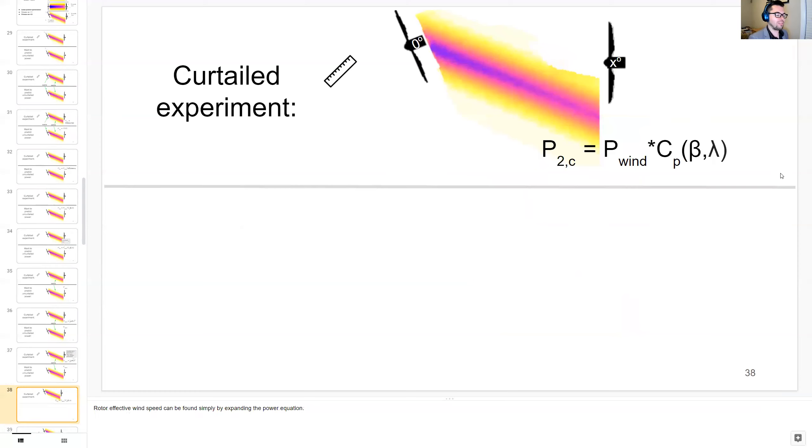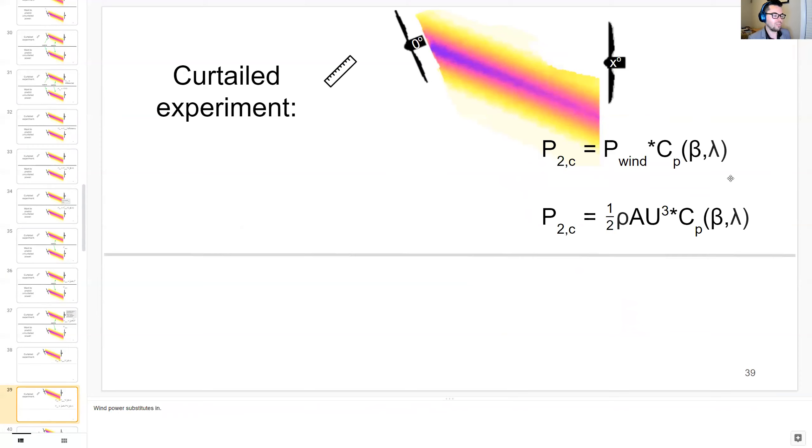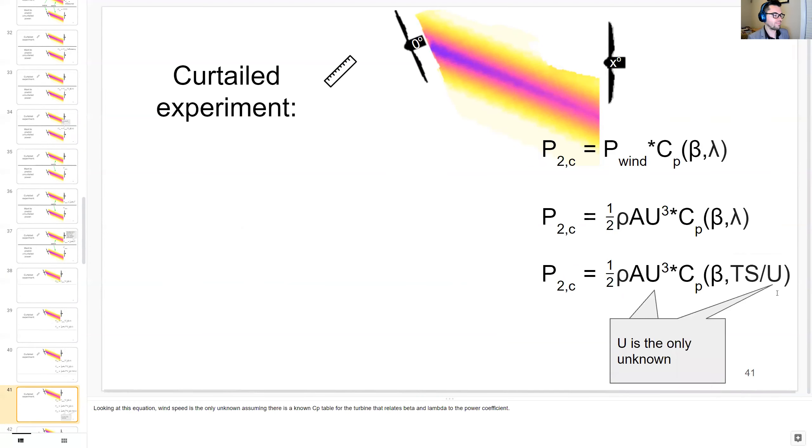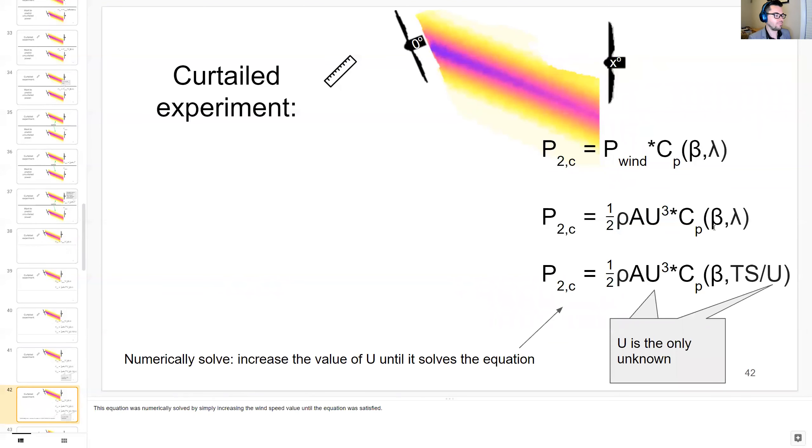Rotor effective wind speeds can be found simply by expanding the power equation as shown here. Wind power equation substitutes in for the power of wind. And the tip speed ratio is expressed as the tip speed omega R divided by the wind speed U. Looking at this equation, wind speed is the only unknown, assuming there is a known CP table for the turbine that relates beta and lambda to the power coefficient. And then from here you could numerically solve by simply increasing the wind speed value until this equation is satisfied.